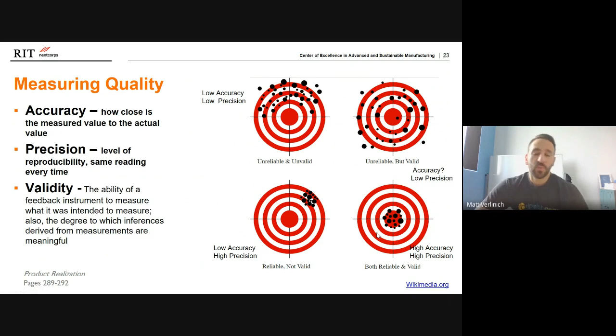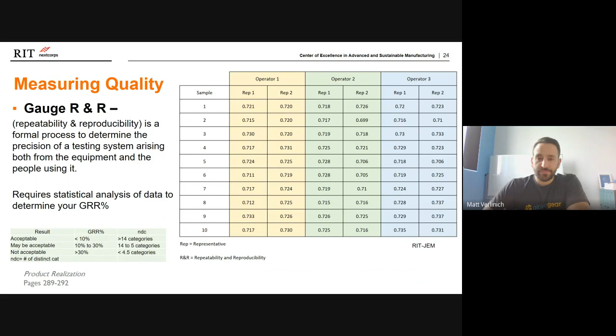needs. So at the end of the day, there is a statistical process for identifying whether you are within your range for accuracy and precision, given the overall process. So that encapsulates both the equipment and the process by which you operate the equipment. And it's called R&R, which stands for repeatability and reproducibility. It's not very difficult to do. You can look up tutorials on how to do this. There are formulas built into Excel to do it, or other statistical programs like Minitab. But the most difficult aspect about it is setting aside the time to actually do these studies, getting multiple different operators to test multiple different samples, all using the same piece of equipment, to then figure out if they're all using the same set of instructions and have been trained appropriately, how well does that training program function in addition to the piece of equipment which you're using.